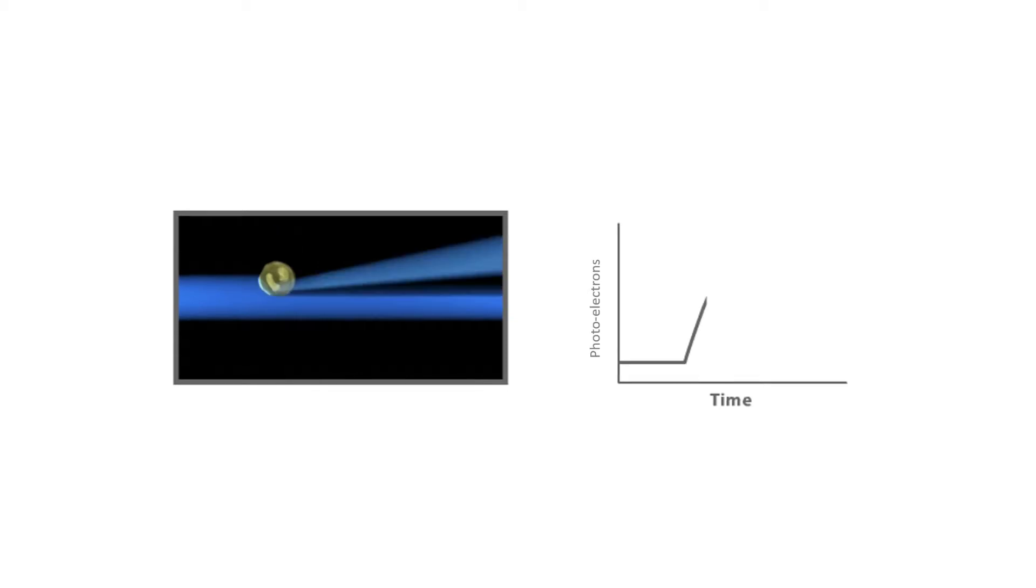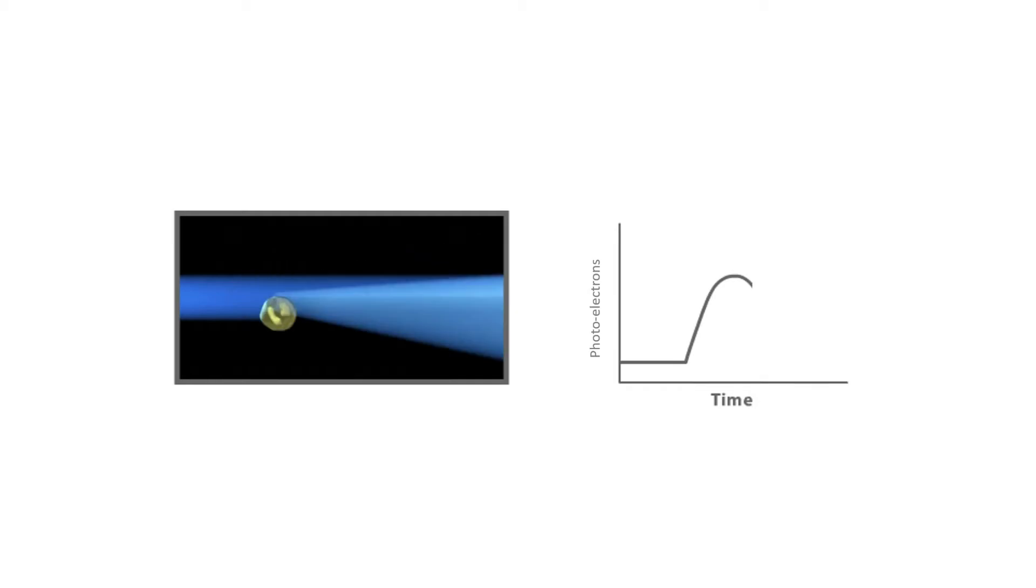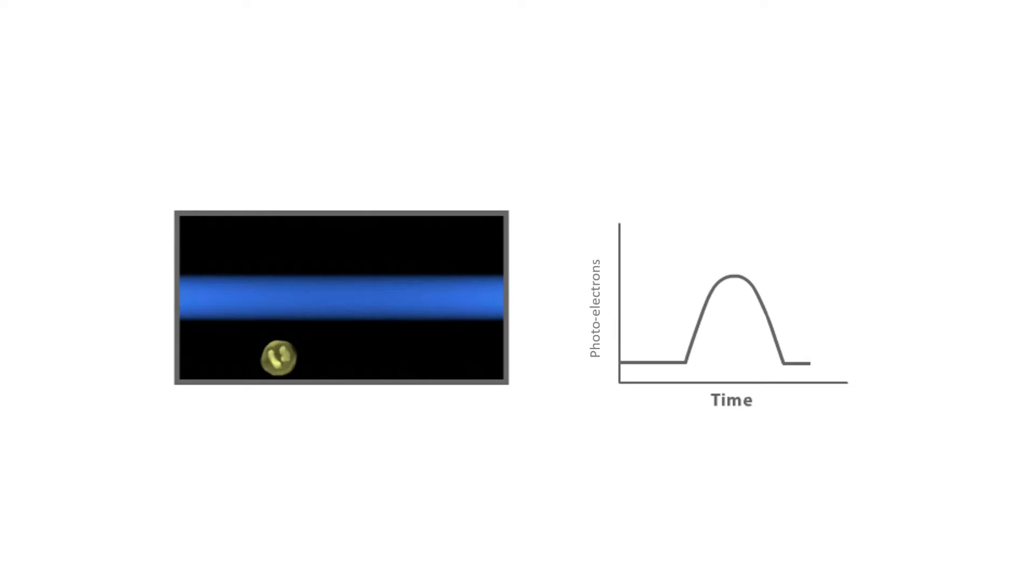In the flow cytometry world, this signal that we're looking at is called the voltage pulse. Inside the detection system, as a cell starts to pass through the laser, we'll start to see the collection of photoelectrons over time. As the cell goes further into the laser, this will peak and then drop off as the cell exits. So essentially that's the voltage pulse, just looking at the collection of photoelectrons on the detector over time.